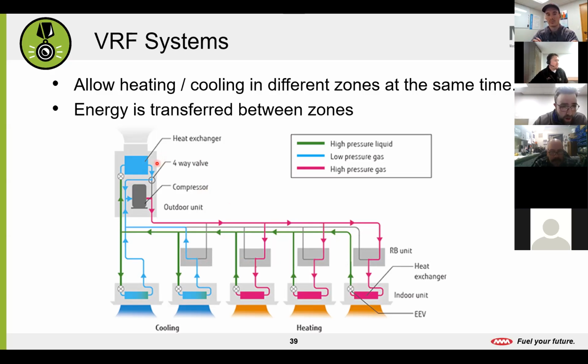If we look at our outdoor unit here, this red line is our high pressure gas, what we like to call our hot gas. When these systems are in heating, our outdoor unit is going to create hot gas, 120, 140 degrees, and it's going to send that gas over to these boxes here. These boxes are what we would call branch controllers or heat recovery units. And pretty much it's just a set of valves that switch between heating and cooling and allow us to have that individual control over our indoor spaces.